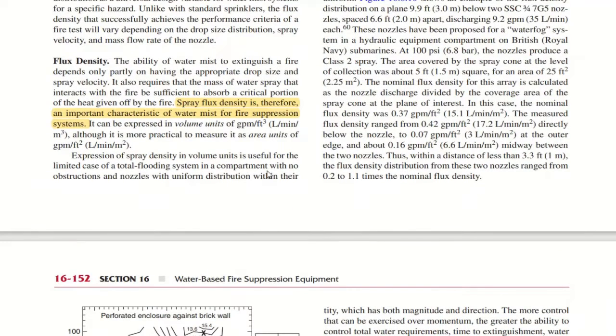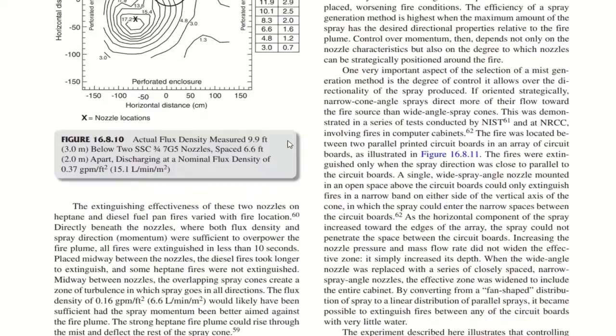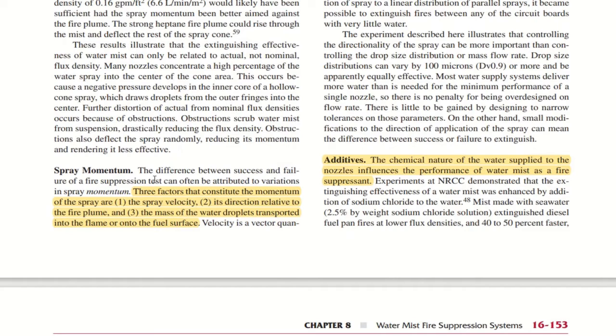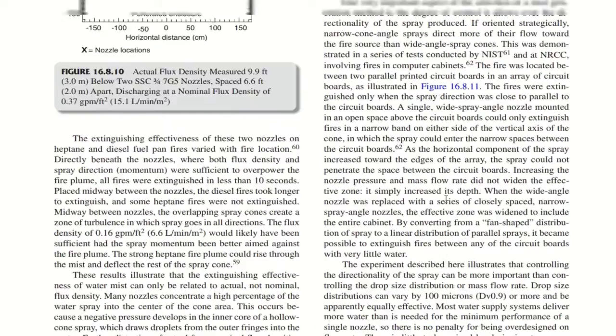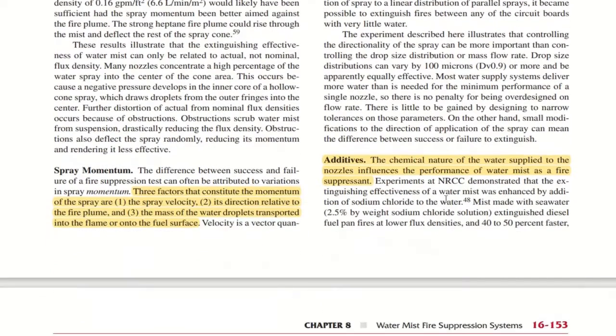So you have flux density. Flux density is therefore an important characteristic of a water mist fire suppression system. You have spray momentum. Three factors that constitute the momentum of the spray are spray velocity, its direction related to the fire plume, and the mass of water droplets transported into the flame or onto the fuel surface. So as I said earlier several times, the highlighted points are very helpful and important for your examination preparation.